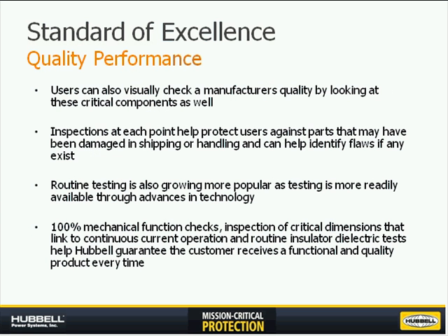What can the users look at? Users can visually inspect incoming cutouts relatively quickly. Most of the checks you're looking for are galvanization, silver plating, things of that nature — this helps protect you against shipping and handling damage as well as identify any flaws that the manufacturer may have missed. Routine electrical checks are becoming more readily available; the mechanical side is almost done 100%, and this is something we're working harder every day to implement in our factories.